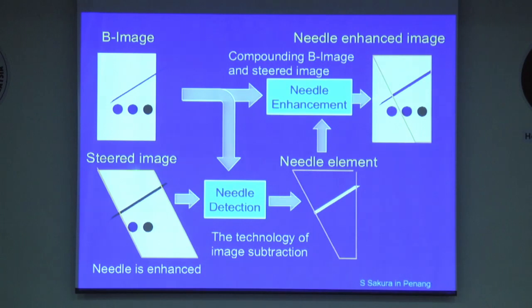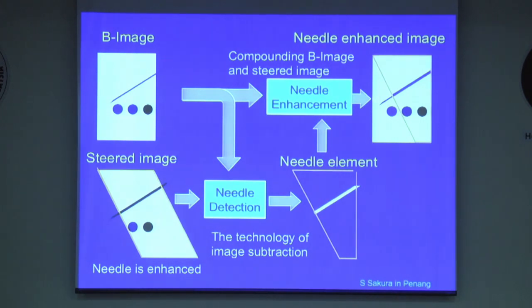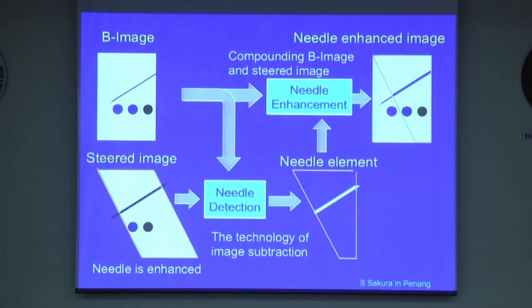On the other hand, with a steered beam, the beam can be vertical to the needle, so the reflected echo directly comes back to the transducer to enhance the needle image. After that, machines usually detect the needle using a technology called image subtraction. Finally, they compound these images to create an image showing both the needle and tissues clearly.